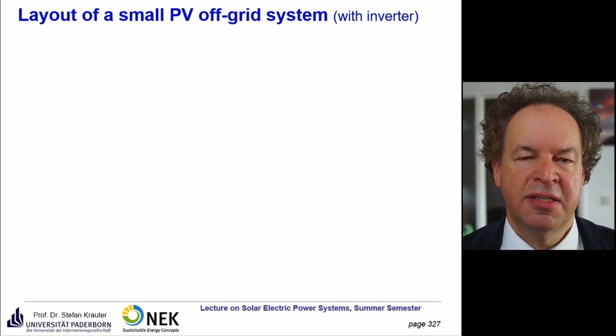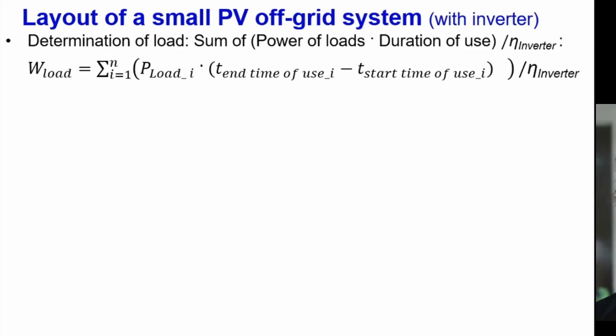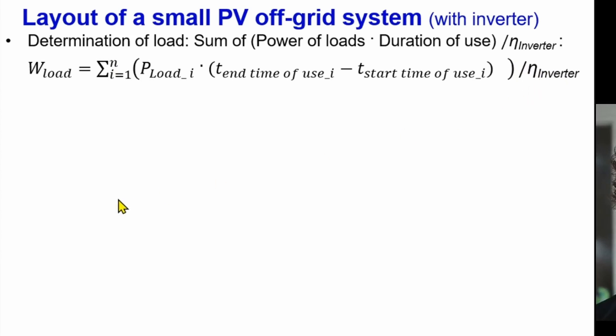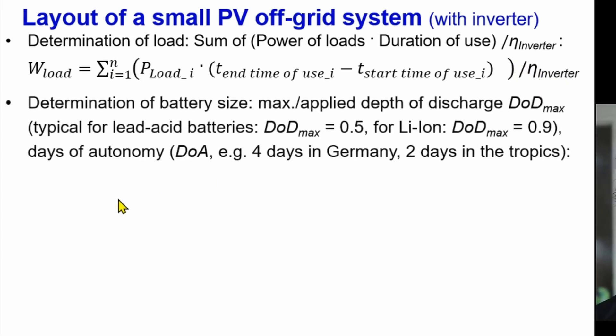The system design plan is covered in the lecture. First, we determine the load by taking the power of each load and its duration of use — end time minus start time — and summing these for all n loads. If an inverter is present, we must also account for inverter efficiency. Then we determine the battery size using the maximum allowable depth of discharge.